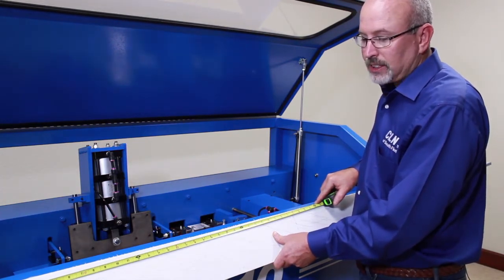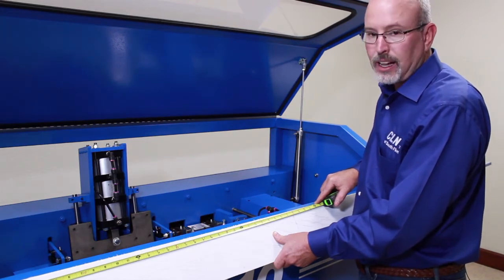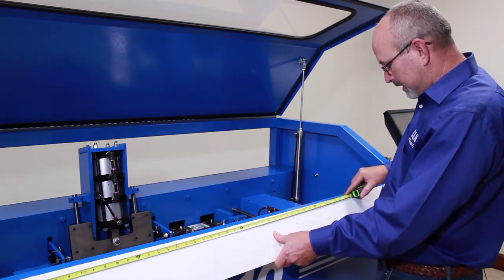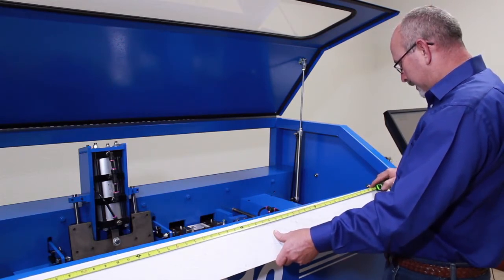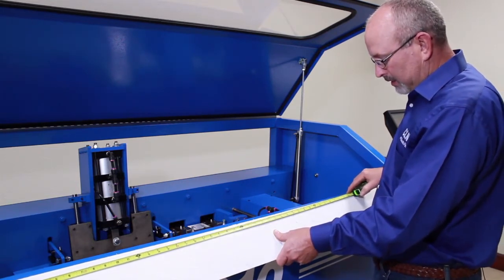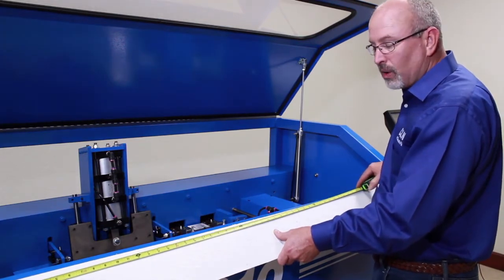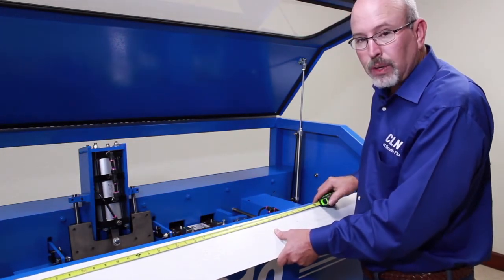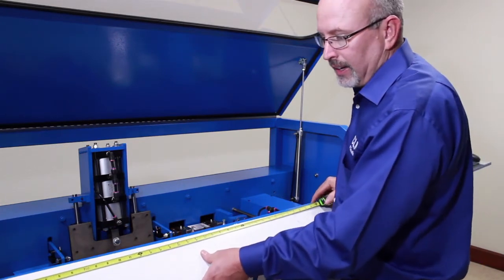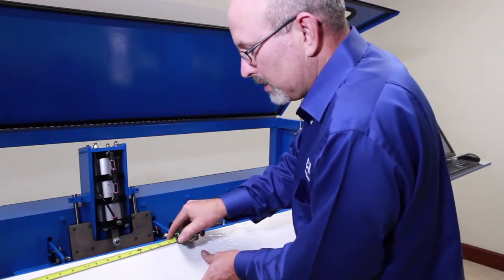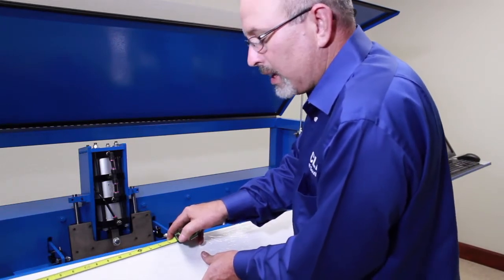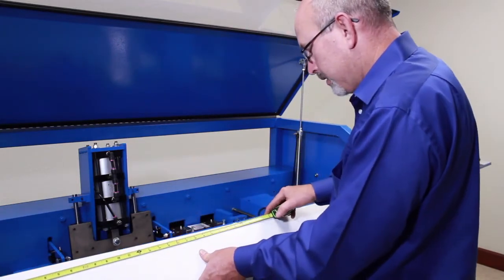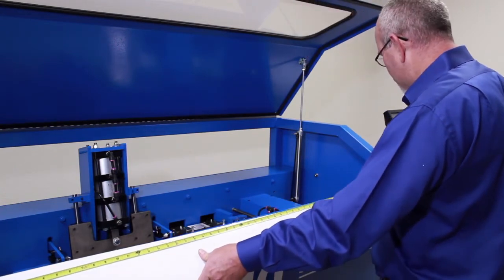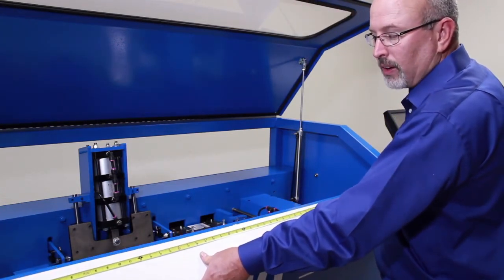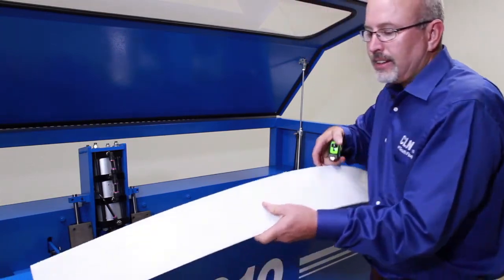So if you don't have a notch exactly on 12 inches, the machine needs calibration. Here I can see that my notches are actually getting shorter by a 1/16 at every 12-inch increment. So I know by measuring this that the calibration is a little short. And I can double check that by coming over to my 12-inch mark. I'm really close to 12 inches. But here I'm short, and I progressively get shorter as I go down the line. So what we're going to do is add to our encoder count value.